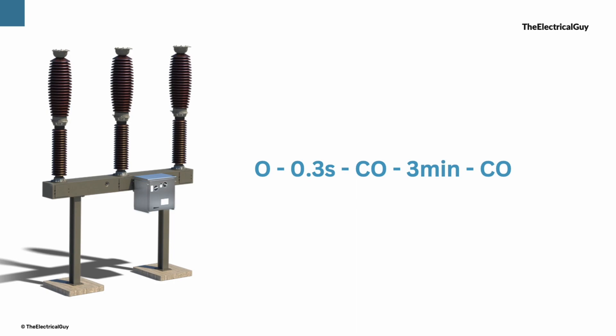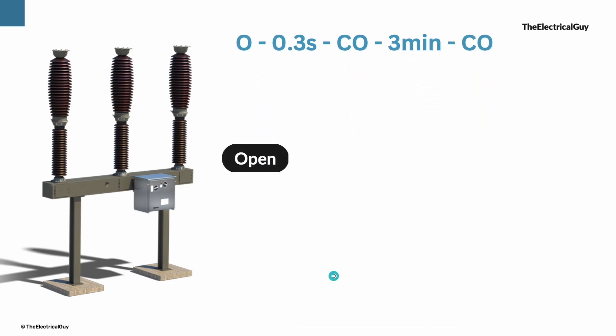So let us break down this cycle to understand. Please note, O represents an opening operation and C represents closing operation of a circuit breaker. Let us say there is a transient fault. Protective relay gives command to circuit breaker and it opens, and that's the first O.